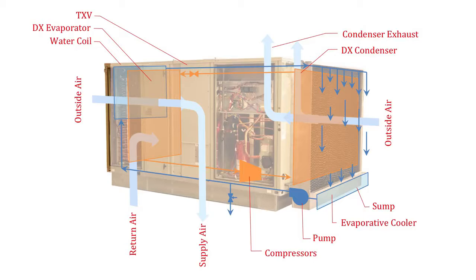Usually that would run through your evaporator coil, be cooled down to your supply air. But here we've added on to the outside this blue circuit. Here in front of the condenser, they add a condenser air pre-cooler. It's an evaporative media about 10 inches deep that covers the entire face and circulates water, which evaporates and cools the air coming into the condenser.